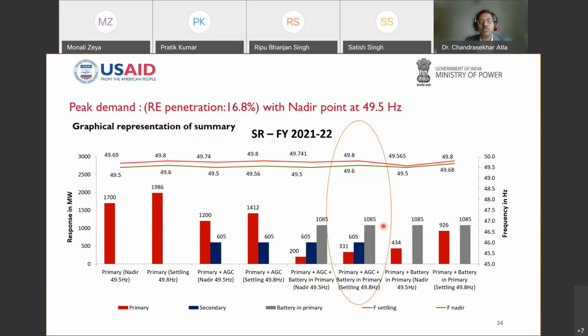And if you take the help of the BES, please note that at no point are we saying the grid cannot maintain, because as long as you deploy the primary reserves, the grid will be stable. But the point here is, if you use the battery energy storage system in the primary reserves, as well as the secondary reserves, as we calculated from the international practice of Europe, around 605 by 21-22, then the requirement from the primary reserves is only 331. Most of the reserves have been deployed by the others, and with only the 331 primary support, you can manage the Nadir frequency of 49.6 and quasi steady state of 49.8.